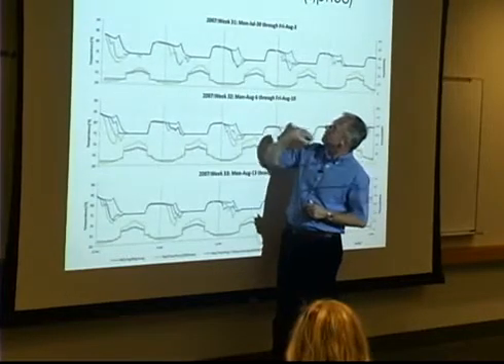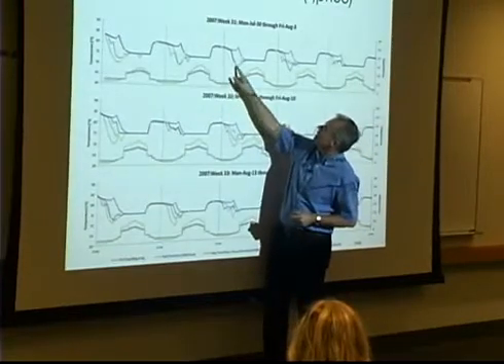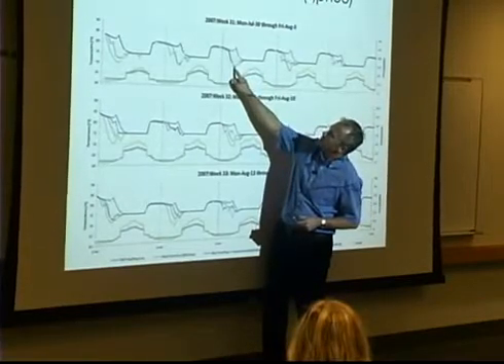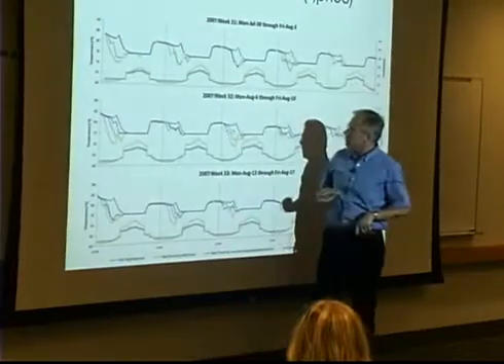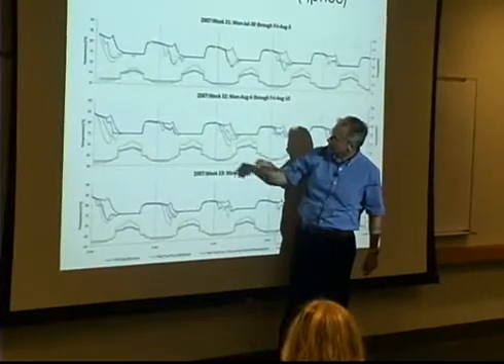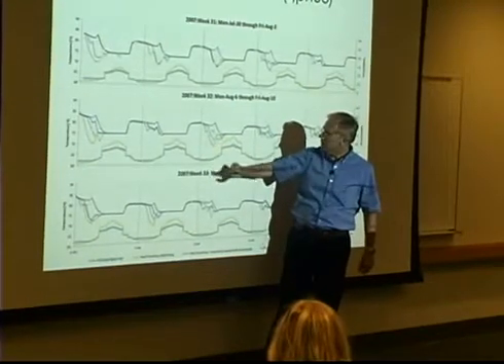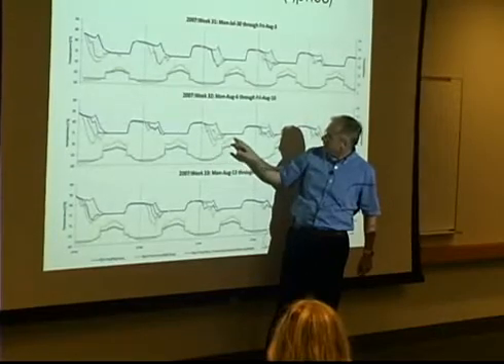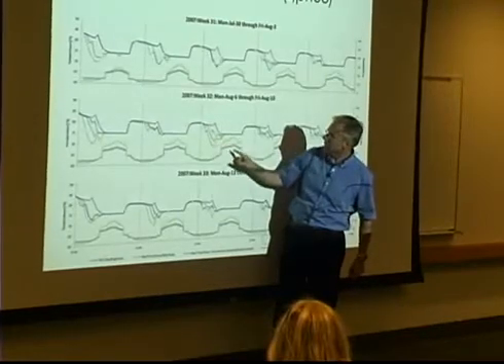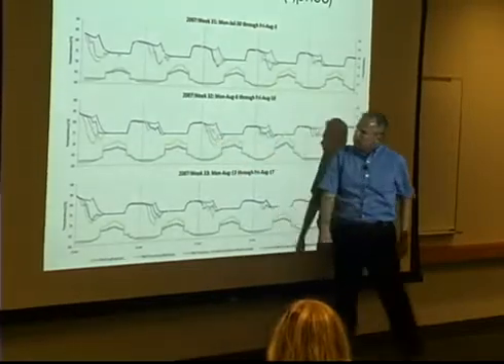And you can see, if I may pick out this Wednesday, the optimal strategy is actually very similar and fairly independent of the pricing here. It chooses a pre-cooling strategy up to 72 degrees. And on other days, let me take the Tuesday and then the week after, you can see the strategy being quite different. So here's a strategy where I have a deep pre-cooling down to 68 degrees. This is taking the building down pretty cold. Whereas with the next pricing strategy, I only pre-cool it to 72 degrees. And at the lowest pricing structure, with the lowest load shifting incentives, I do the least pre-cooling.